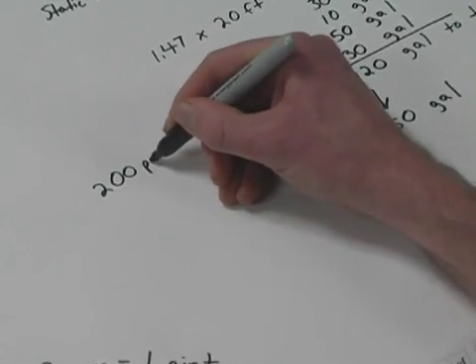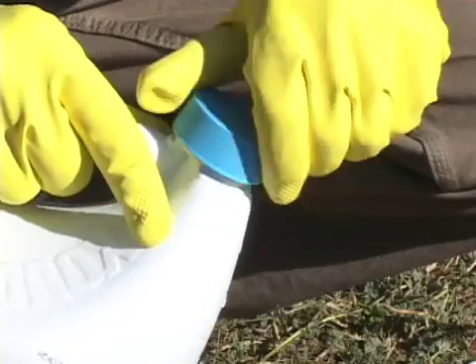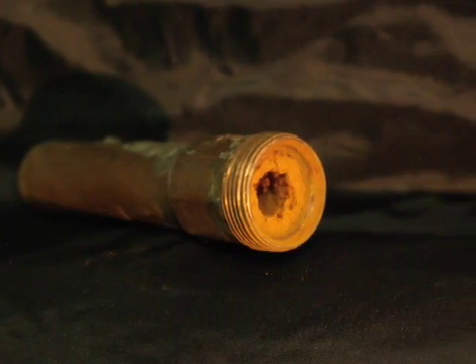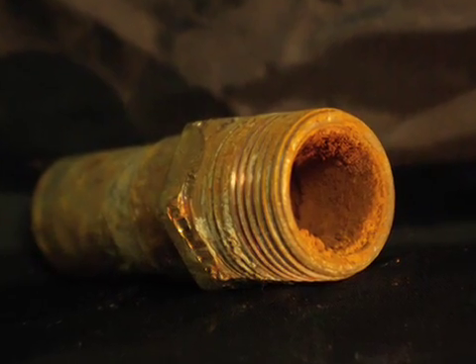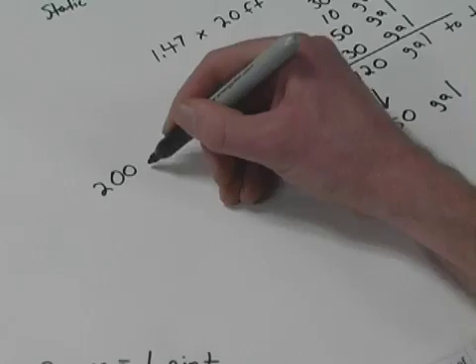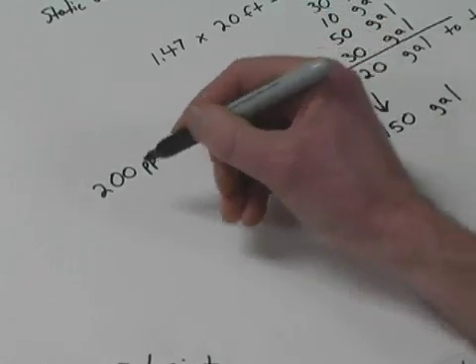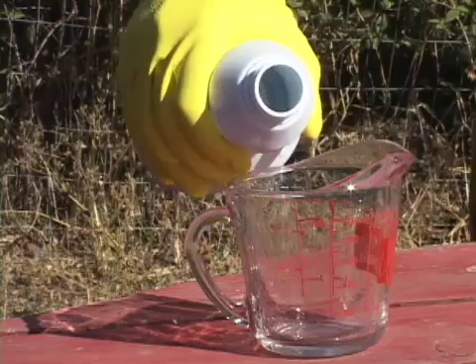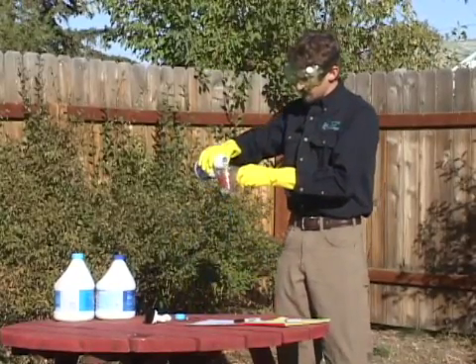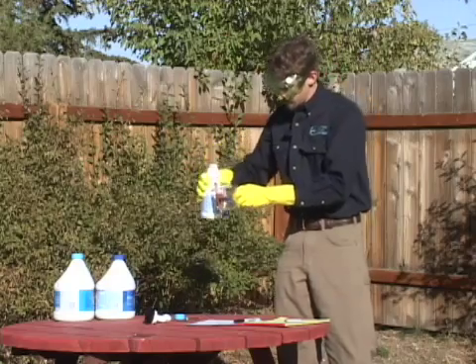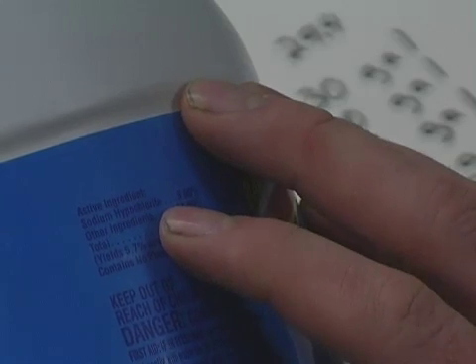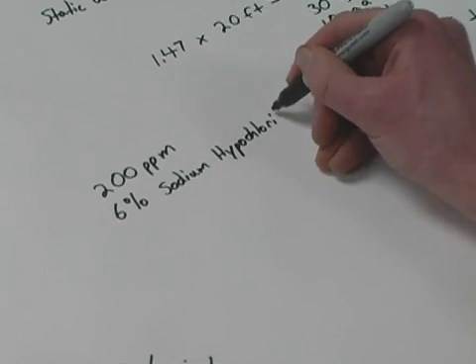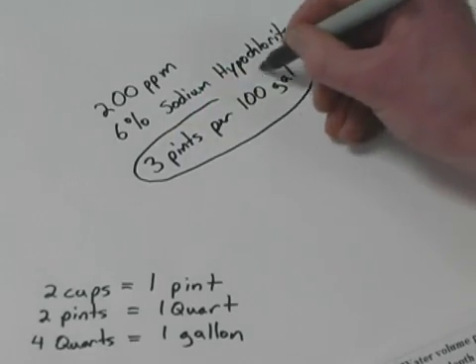Our goal here is to get all of the water in the distribution system up to 200 parts per million of chlorine to kill the bacteria. Higher chlorine concentrations may be necessary in special cases — for instance, if you have determined that you have iron bacteria fouling in your system. So next we need to determine how much chlorine to add to get 200 parts per million. Chlorine is available in a variety of forms including concentrated liquids, pellets, and liquid laundry bleach. People commonly use liquid laundry bleach, so that's what we will use for this demonstration. Do not use any type of scented bleach or any bleach mixed with detergent or other additives. Typical liquid laundry bleach is 6% sodium hypochlorite, which means we need to add at least 3 pints per 100 gallons to get 200 parts per million of chlorine.